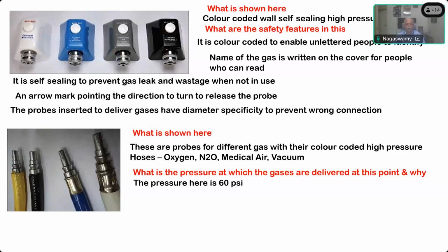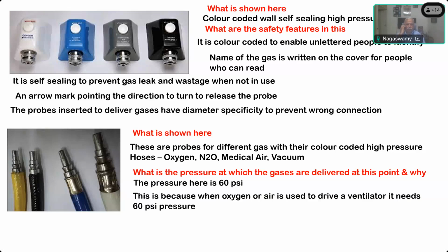The reason the pressure is 50 to 60 psi is that when oxygen or air is used to drive a ventilator, it needs 60 psi pressure. Nowadays, all the anesthesia workstations come with their own ventilators. Majority of them can generate the pneumatic power by their own mechanism. But earlier machines used to depend on the oxygen supply, which would be partly diverted to the ventilator to drive the bellows. So earlier models utilized this air or oxygen for their functioning, and that can work only when there is a 60 psi pressure. So that was standardized.